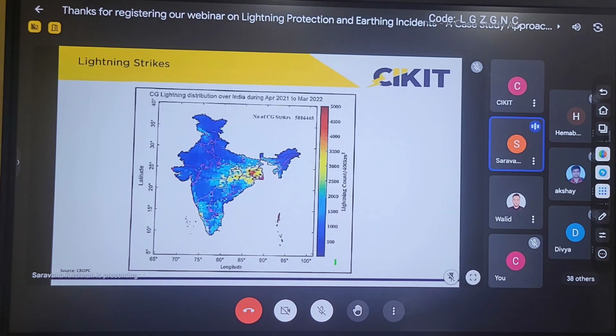If the same kind of building is located in Chennai, another in Rajasthan, and another in West Bengal, then the risk will be more for the West Bengal building than for Rajasthan and Chennai. So even though the building dimensions are the same, the risk mainly depends upon the number of lightning strikes in that particular region over the year. This is one of the important parameters that has to be considered while performing this design.